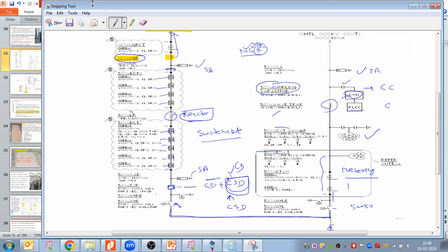And now, coming back to why NGR is required. This is when we have a line reactor. Whenever I have the bus reactor, this is my circuit diagram for the bus reactor. So, just the bus bar and then breakers, disconnector, breaker with CVT and then CT, and then disconnector, and taking the circuit out, and then isolators or disconnectors, earthing switch directly connected to the shunt reactor here, and then it is connected to the ground. There is no NGR coming here, right?